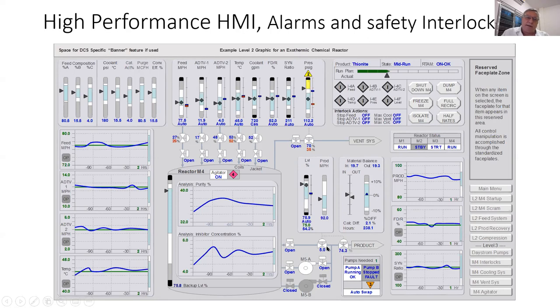Some others tell there's a discussion about the meaning of what you see here, white and gray. Actually, in that view, it should show that white means it is on or active, or a valve is open. Someone explained that to me one time, when I had to do this high performance HMI interface for Amazon at a BASF plant in Germany. That was one of my last biggest projects in Germany. And I had some discussions with the people who required these, and then we discussed how we should handle the color for the motor or for a valve. Mostly, we have done this with red and green, but we don't want to have colors, so we have to go with gray, or let's say gray and white.